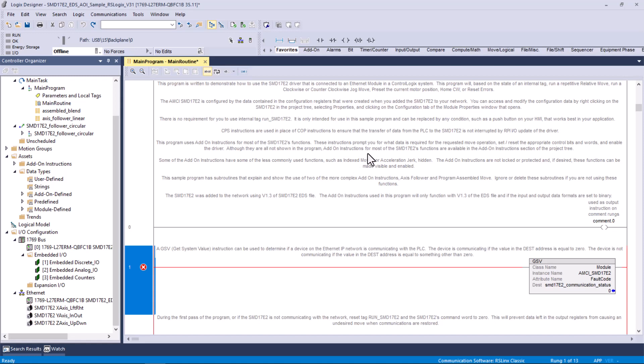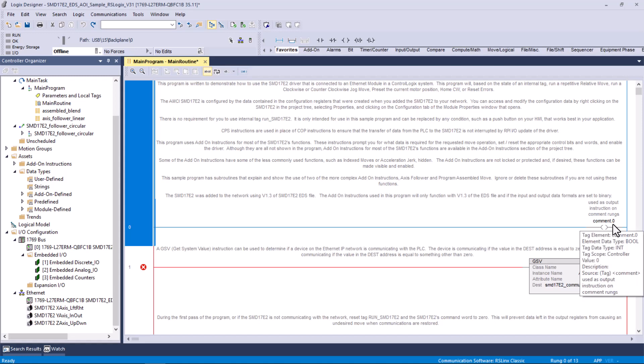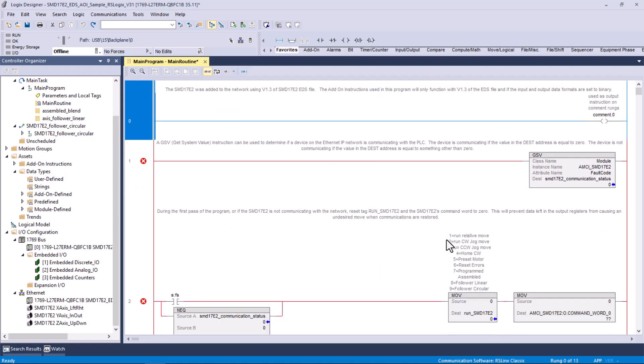What we have in this main routine is a group of functions, logic that will execute functions. Now, this first comment, that's an anchor for comments, and I do this myself. I'll create a tag, a DINT, 32 bits, called comment, and then I use the bits 0 through 31 to anchor comments, so any place I want to comment, and I don't want it to move. I want it to stay right there in the logic. I will use an unconditional true rung to an OTE, and I will reference it to the tag comment, decimal point, and then 0 through 31.